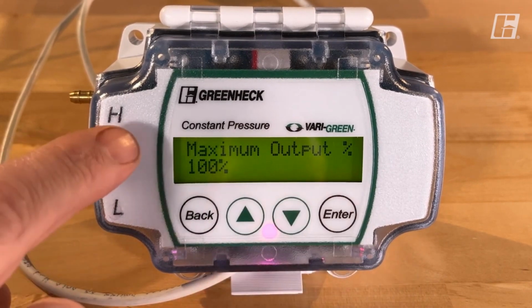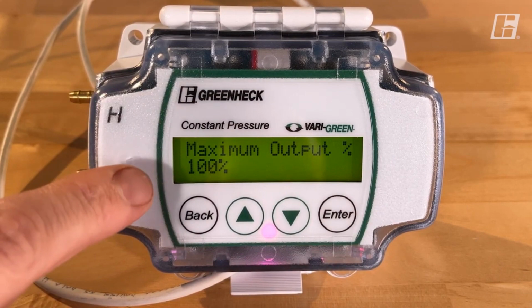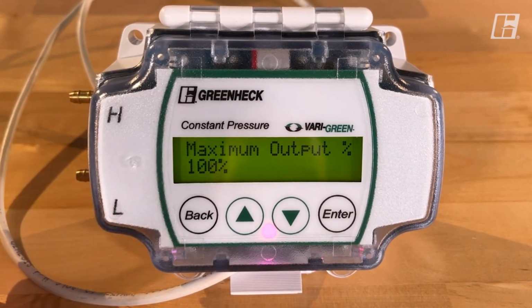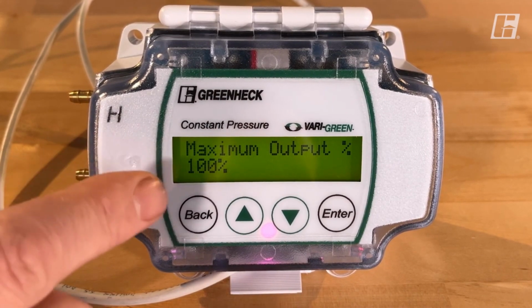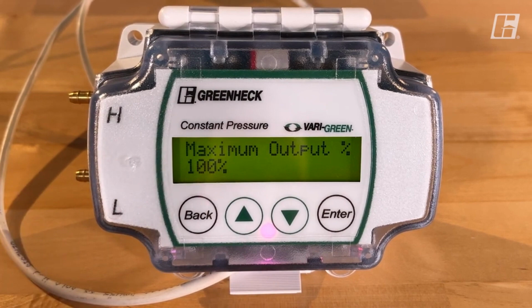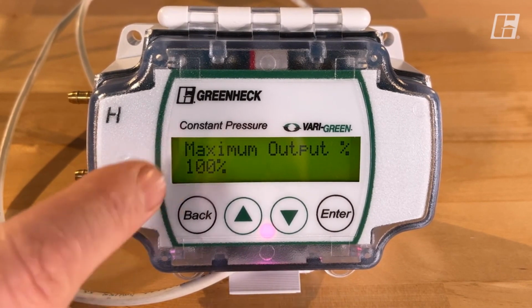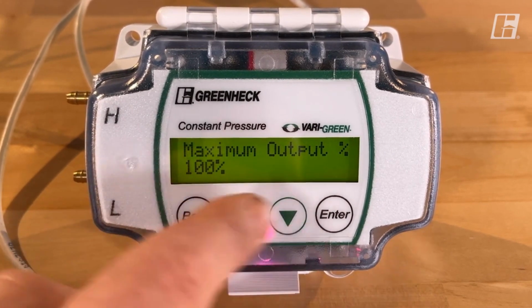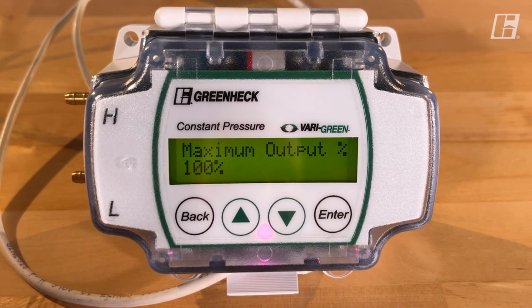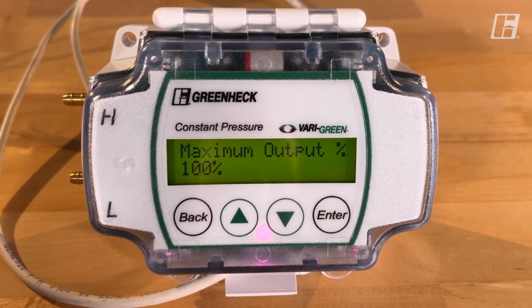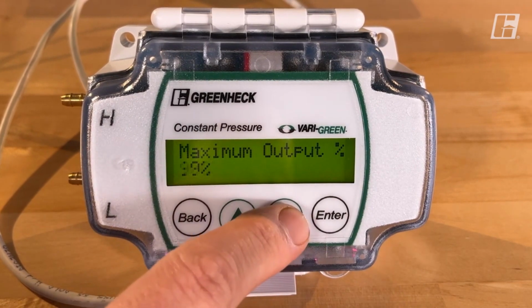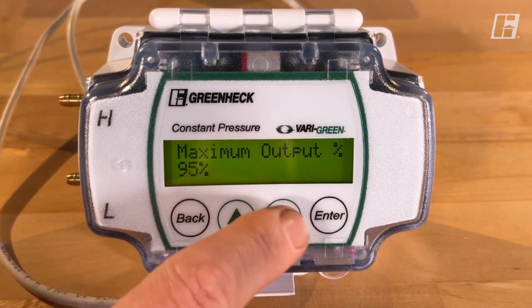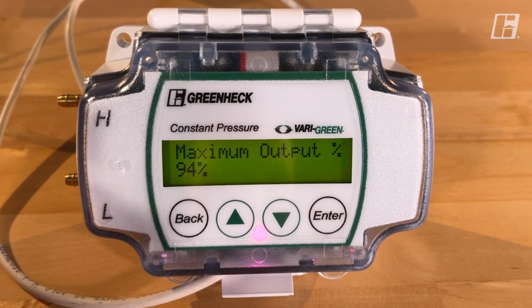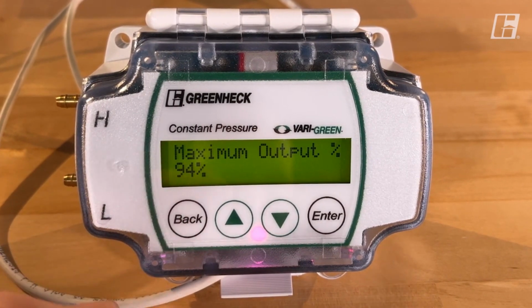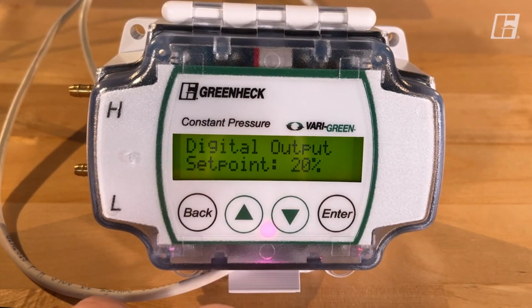The next set point is our maximum output. So we're basically defining the range the fan can operate in to maintain your pressure set points. The minimum, we can go from 20%, and this is up to 100%. Now you might want to reduce this if you didn't want to move air that fast. You wanted it to control the pressure, but you wanted to take a little bit out of the speed of the air. So you're going to reduce that top end speed the fan is capable of using.